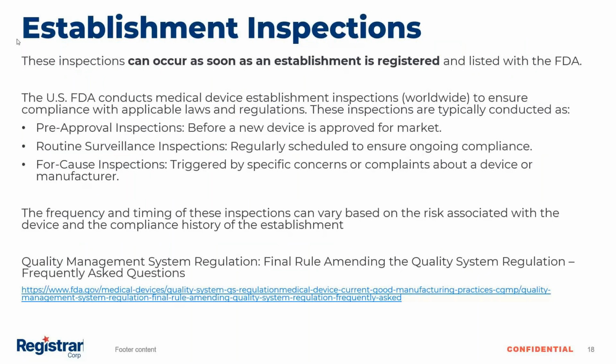That being said, finishing your establishment registration can also trigger inspections going forward at any time. And with any time, I mean really any time. So inspections can occur as soon as the establishment is registered and listed with the FDA. The FDA conducts medical device establishment inspections worldwide to ensure compliance with applicable laws and regulations. That means they are looking if you have all the GMPs in place, if you keep records and all that paperwork.